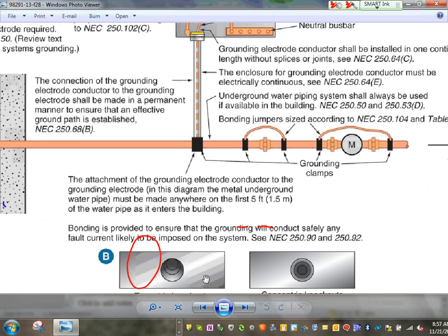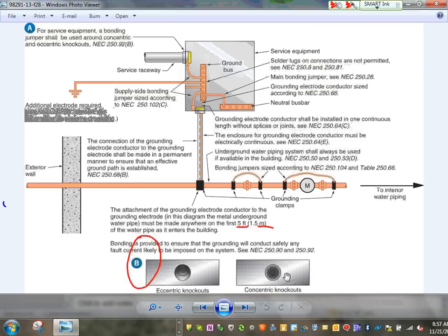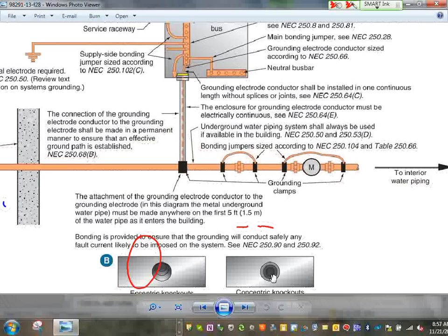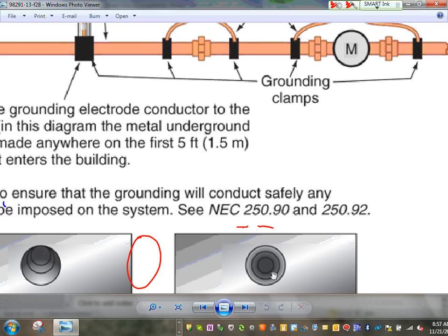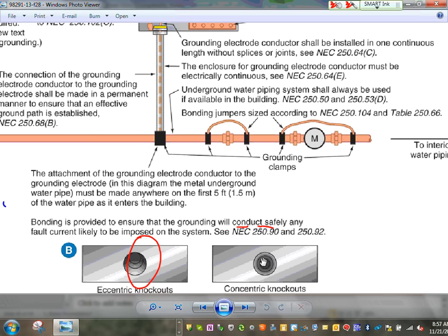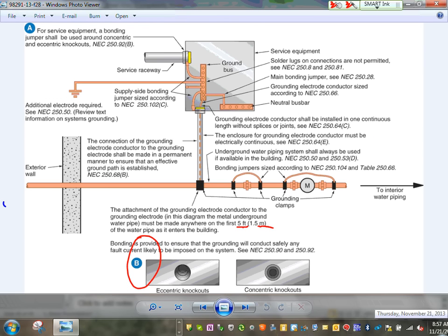This is where we talk about eccentric or concentric knockouts. If the hole matches the conduit, I'm sure, Adam, you guys did it when you were doing it there. If the hole matches the conduit and the system is 480/277, you do nothing unless that's at the service. Otherwise, you have to bond the conduit.